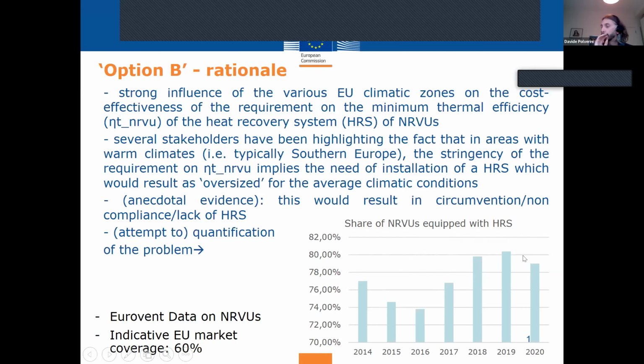Having a look to this trend, one could see that indicatively, as of 2016, where indeed we had the requirements entering into application, so the compulsory presence of the heat recovery system, as of that year, we had an increase, perhaps now under stabilization, of the units having the heat recovery system. So we could, I would say, link this to the entry into force of the application, so to the effect of the regulatory requirements. Obviously, we still see that we are at the level of 80%. So what about this 20%?